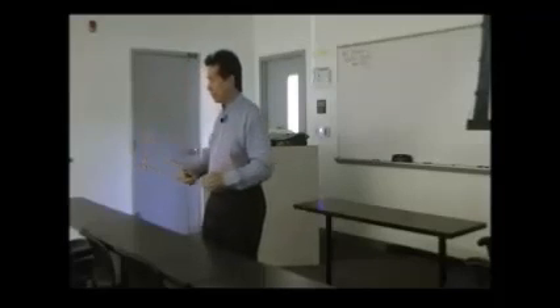Services are often complex and difficult to inspect in their physical condition. So in some cases, after you build it, and this gets back to accessibility and maintainability, after you install that particular fan coil unit above the drop ceiling and seal it up and walk away from it, remember we talked about the equipment register and the equipment inventory? Getting up to this piece of equipment that's above the drop ceiling and between piping, you have to remove sections of the ceiling grid to get up into it, and to assess the condition is going to be extremely difficult.